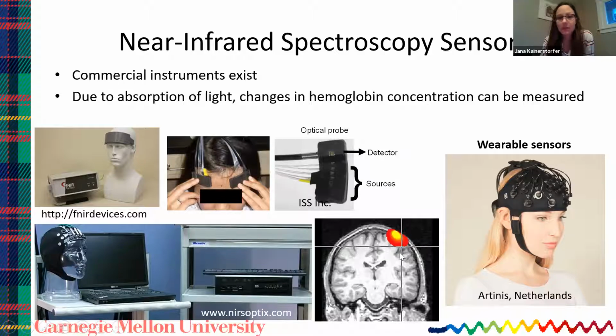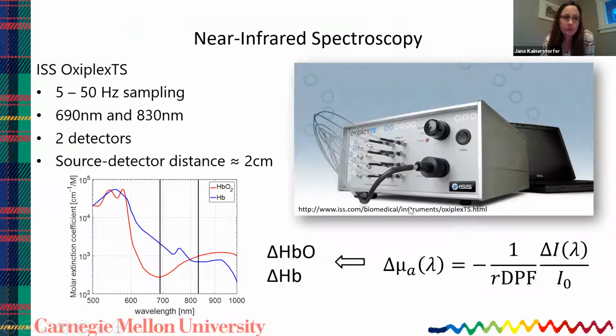That red blob itself is already telling you it's a pretty low resolution imaging method. But what we can do is build things relatively small and portable. There are companies like Artinis that are building wearable sensors where the battery is all in a backpack and people can walk around with those optical fibers on the head. The instruments we use typically have a sampling frequency somewhere in the tens of hertz. The typical wavelengths we use are 690 and 830 nanometers, so in the near infrared range.